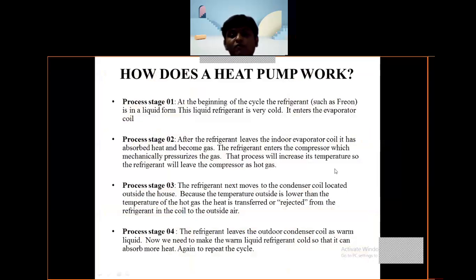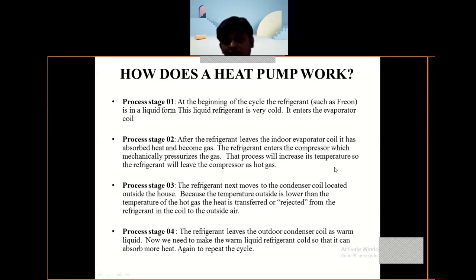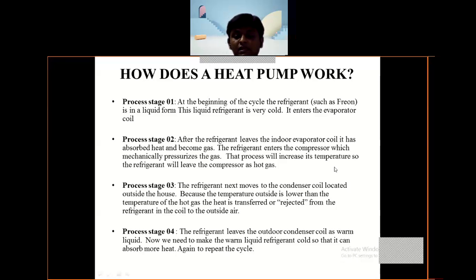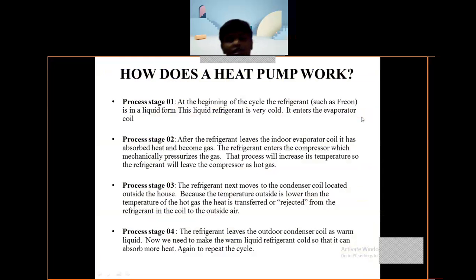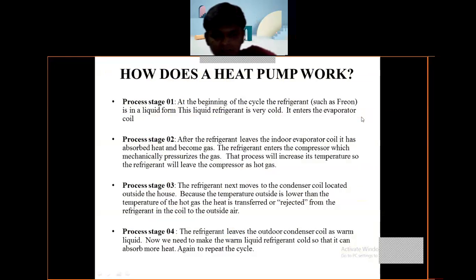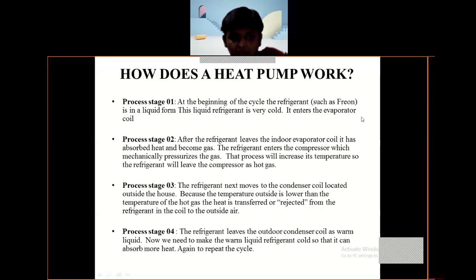Process number two: after the refrigerant leaves the indoor evaporator coil, it has absorbed heat and becomes a gas. The refrigerant enters the compressor, which mechanically pressurizes the gas. This process increases its temperature, so the refrigerant leaves the compressor as a hot gas. The refrigerant next moves to the condenser coil located outside the house. Because the outside temperature is lower than the temperature of the hot gas, heat is transferred from the refrigerant in the coil to the outside air.